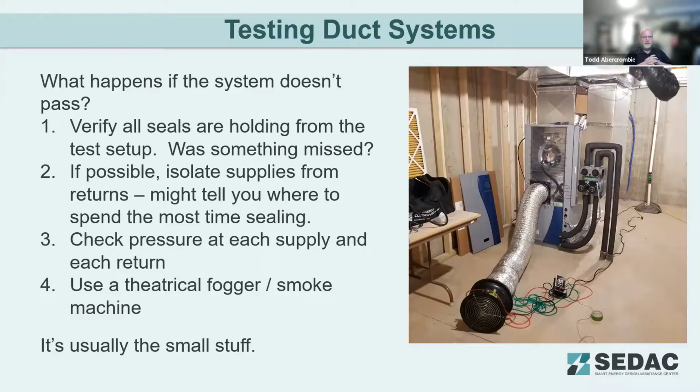It is a useful test, but having done it in reality, it can be a bit of a mess, because after you let it run for so long, that fog literally will fill up the room, the basement, the house, the building, wherever you're in, so much so you can barely see 10 feet in front of you. So we try to save that as the last resort if we can't figure it out in other ways. So in my opinion and experience, start with the simple and the quick first, and then work towards that if you need to.